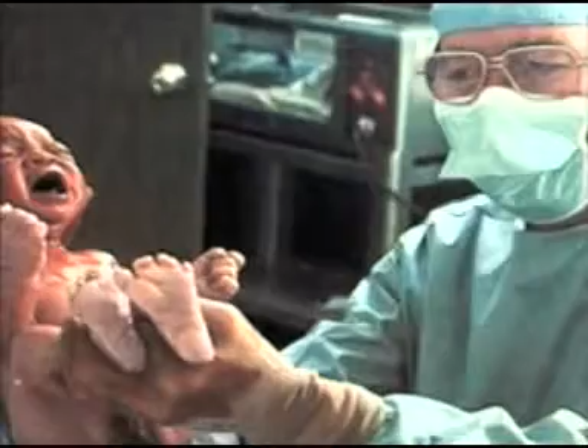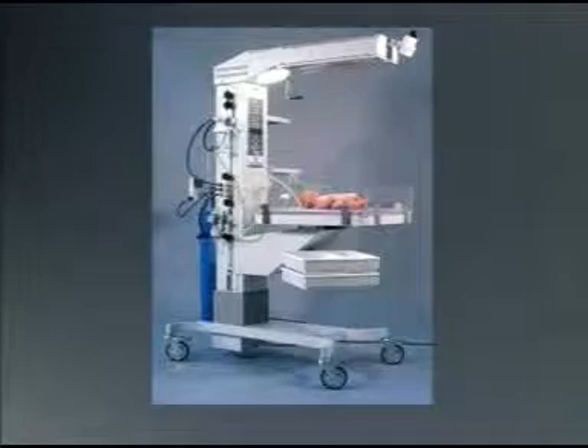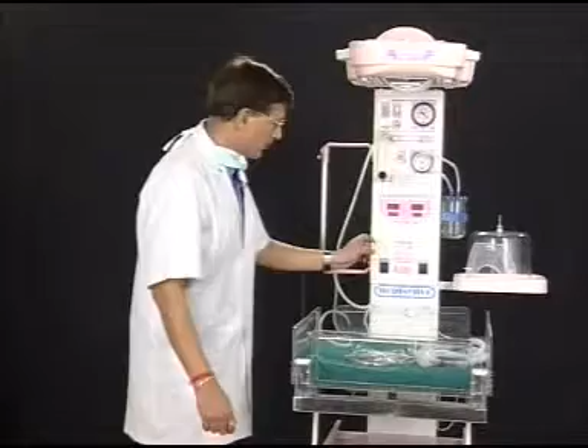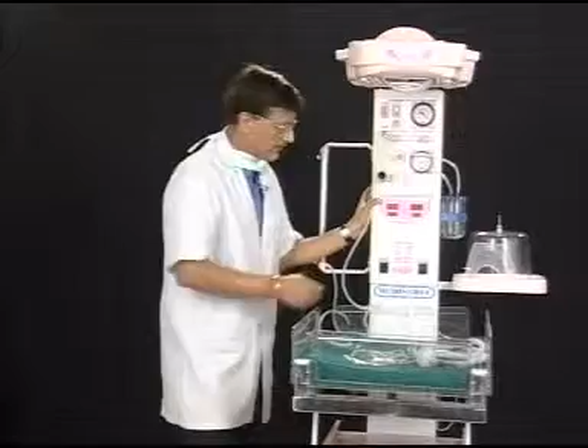After the baby is received in a pre-warmed linen, the baby is moved to the baby area and is kept under the warmer for further resuscitation. Before the baby is received, we must switch on the warmer. We must set in this machine an air temperature of 32 degrees centigrade. The green here shows the set temperature and the red is showing the actual temperature, so that when the baby is received, this must have built up to 32 degrees centigrade.